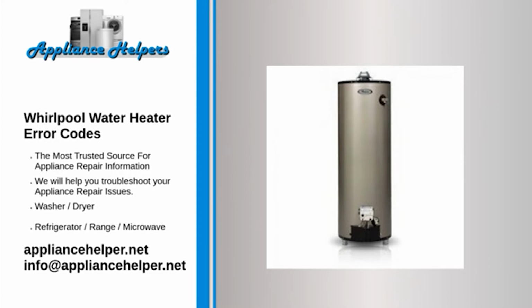Problem: electrical power on with the tank empty or not completely full of water. Fix: turn off electrical power at the breaker. Open a hot water faucet in the house and then turn the cold water supply onto the water heater and allow time for the tank to fill with water.